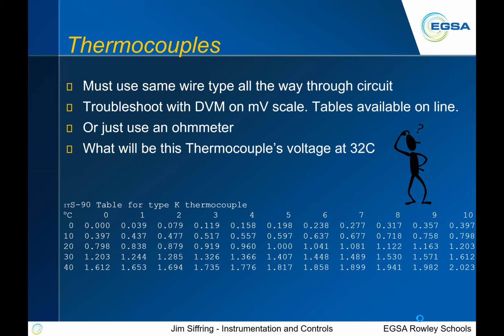So we've got a thermocouple. This particular chart down here will show what would be the voltage output on this particular thermocouple at 32 degrees. Well, we'd go over on the left-hand side, we'd see 30, and we'd go across to the 2 for 32, and we'd have 1.285 millivolts.